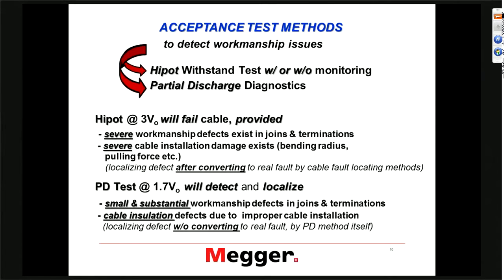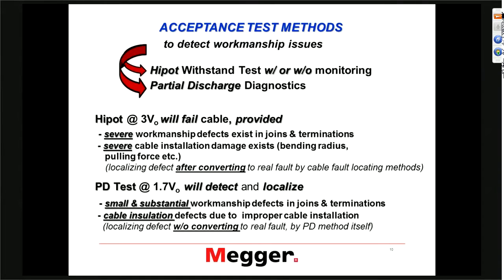If we have a localized defect, we basically convert that localized defect by the hypot test to a real cable fault, then we locate the fault, cut that piece of cable out, and put a splice in. That is what a hypot test can do for us — it's like a screening test to screen out the real severe and bad situations. But it cannot tell you, by passing, what kind of a margin the test is passing. It's typically a go/no-go test.